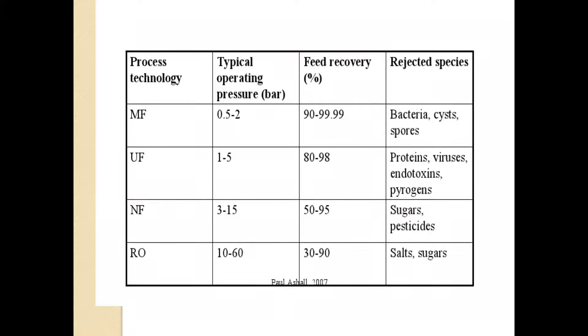Regarding rejected species: microfiltration rejects all bacteria, cysts, and spores. Ultrafiltration rejects proteins, endotoxins, and pyrogens. Nanofiltration rejects sugar molecules and pesticides. Reverse osmosis rejects salts and some sugars.